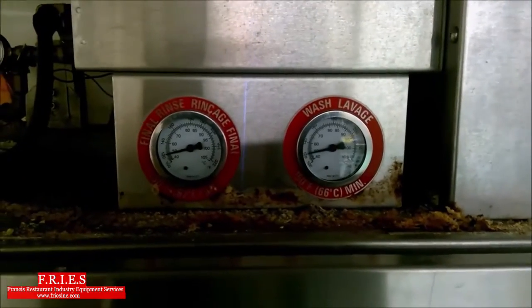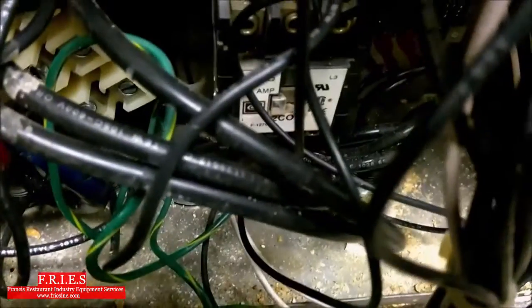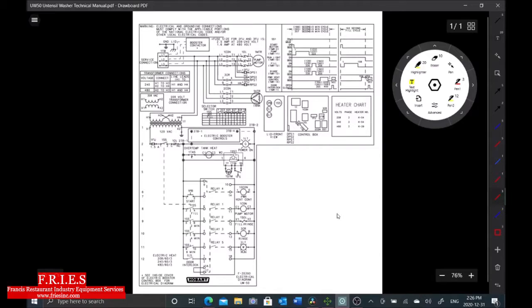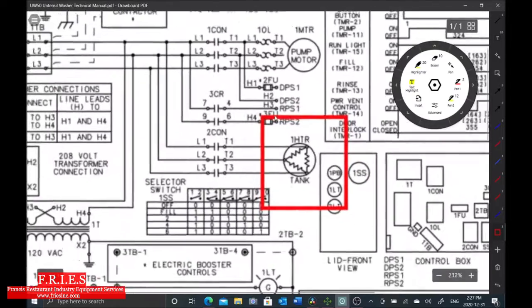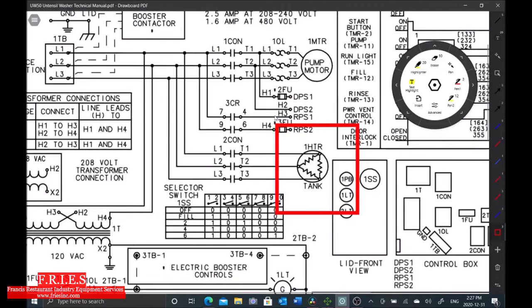So now we're going to go check our visual cues before we go to the schematic. First thing, you can see the wash temperature is not increasing from 120. And that contactor plunger is not pulling in for our tank heater. Alright, so we're going to start by identifying the load. In this case, that's this heater right here. So I'm just going to draw where the power should be. We're just going to work backwards. I always find working backwards is the easiest way. Find the load and then just follow it back.